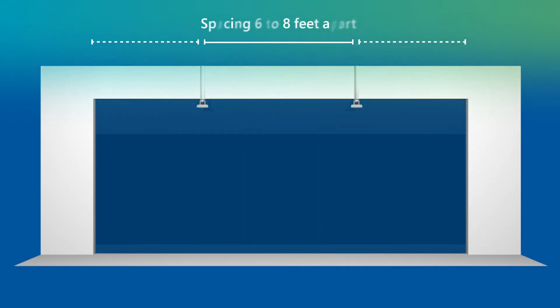If the panes of glass are separated or framed using butt joints, then a window sprinkler is not required for every pane. In installation, each sprinkler should be placed a minimum of six feet apart and a maximum of eight feet apart.